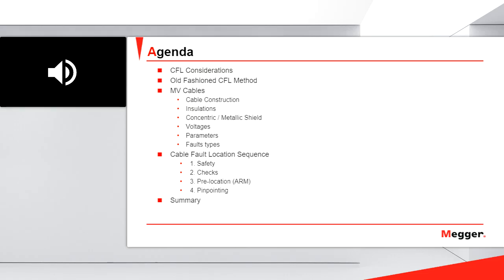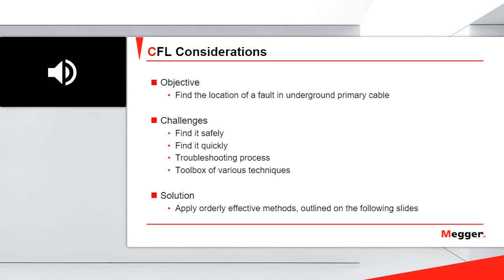Okay, let's start with the cable fault location considerations. Of course, the objective is always to find the location of a fault in a medium voltage cable, in an underground primary cable. And the challenges that we will face are to find the fault safely and quickly, and you will see that fault location is a troubleshooting process. And depending on the fault we have in our cable is the tool we will use. Okay, so fault location is a troubleshooting process in which we have several tools depending on the fault we have in our cable.